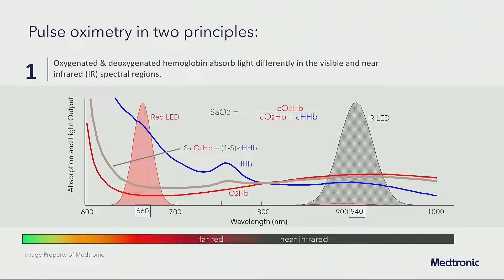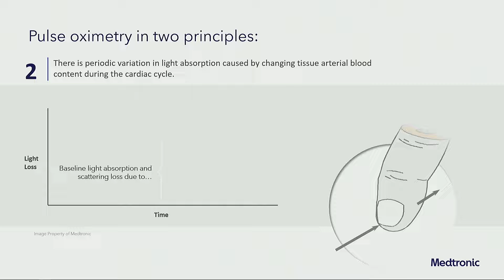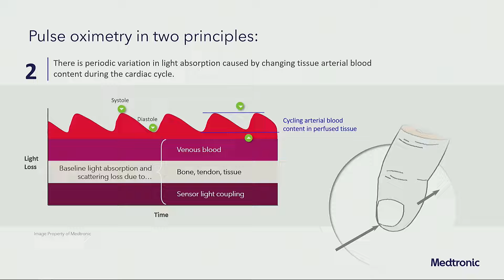The second key principle is that there's variation in that light absorption that's related to pulsation. So as the light is going from the transmitter to the detector, it's going through tissue. And so that light is going to get dispersed, lost. Essentially, you can think of the light being lost. There's going to be some baseline light absorption that's related to the sensor itself, bone, tendon, and tissue, and then venous blood. All of us know that venous hum, right? So the venous blood is not pulsatile. All of that is noise. What we're interested in is that pulsation. And it's that difference in systole and diastole, that cycling blood, those changes in signals that the pulse oximeter is detecting. And that's how we derive the SAT.